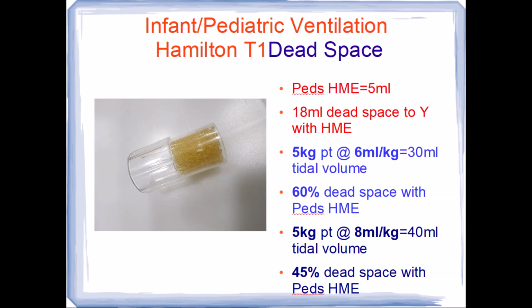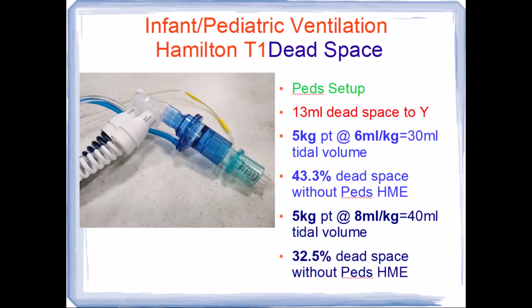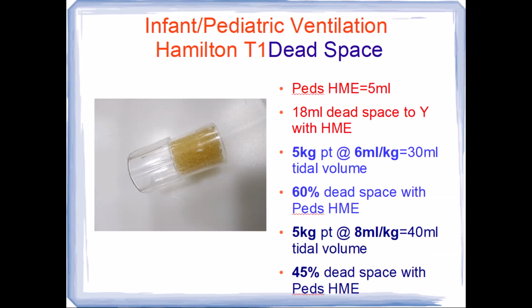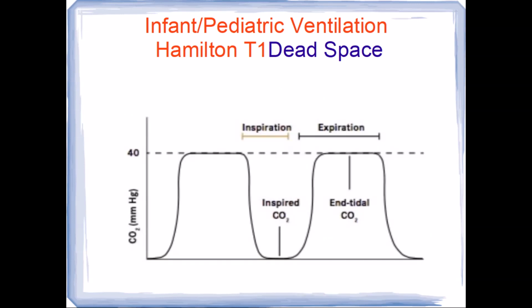And then again, the 5 kilo at 8 milliliters per kilo, optimizing that tidal volume, that's up to the 40 mL tidal volume, is down to 45% dead space versus the 32.5. So you can see the increase just by adding one simple little piece of equipment in here, how significant that is. So what do we have? How can we tell with the equipment that we have whether we are high with the dead space ventilation or we have too much dead space ventilation?